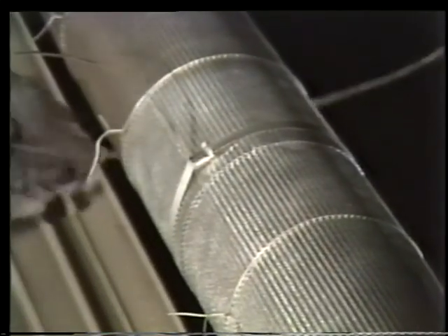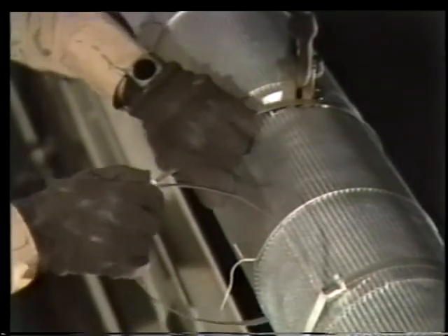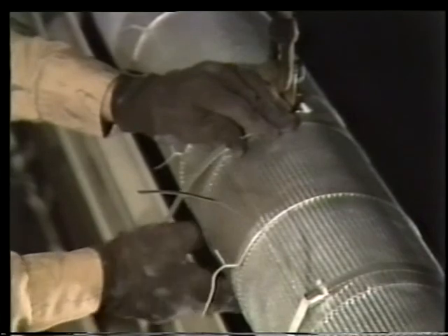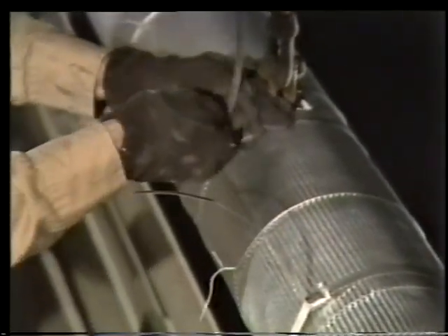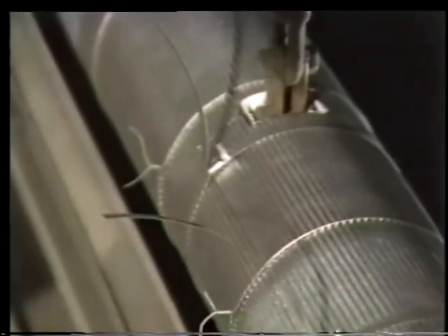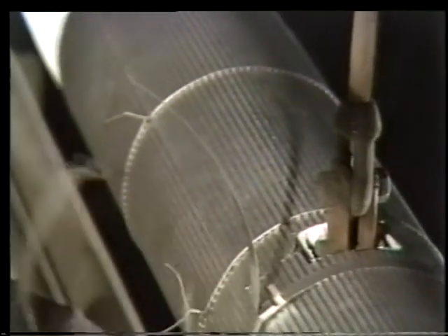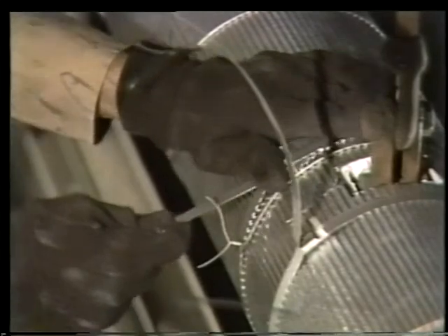Bands are placed 1 foot apart, about 1/3 of a meter. Additional bands may be needed to hold down flaps from special cuts, like the cut for this hanger and the ends of the jacket. The first step is to position the bands. When they're all in place, they'll be tightened with a special tool. The mechanic wraps the band around the jacket and pushes the free end through the slot. He pulls on the free end to cinch the band tight and bends it up so it won't slip back through.